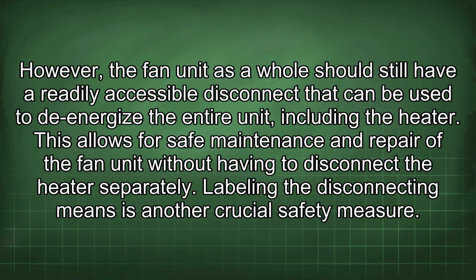However, the fan unit as a whole should still have a readily accessible disconnect that can be used to de-energize the entire unit, including the heater. This allows for safe maintenance and repair of the fan unit without having to disconnect the heater separately.